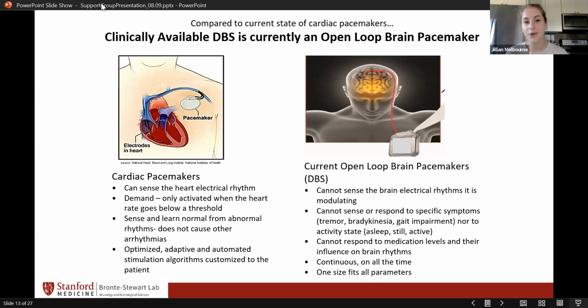That's a wonderful question. So the frequency switching algorithm is only one of several algorithms that we use. The reason why we're interested in 140 hertz and 60 hertz is because 60 hertz specifically has been shown to help ameliorate freezing of gait and gait impairment. However, it at times can exacerbate tremor. And so in this algorithm specifically, it's adapting between 140 hertz and 60 hertz whenever someone begins a freeze. As soon as the algorithm senses that someone might freeze, it will switch them to 60. And when they're no longer freezing, it will put them back on 140, with the idea being that the 60 hertz should be able to kind of power them out of a freeze, but they'll be on 140 most of the time so that their tremor isn't being exacerbated. Got it. That helps. Thank you.